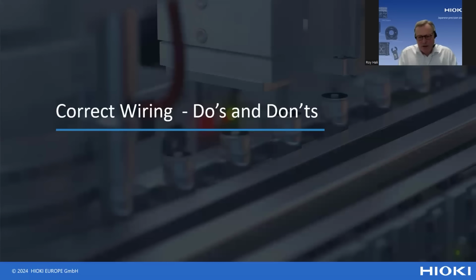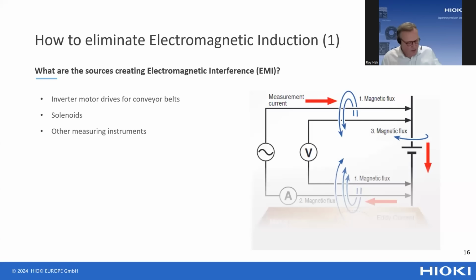So we start with the wiring first. What influences can the wiring have? The first thing to consider is that electromagnetic induction can influence the test results. How does that work? The battery tester uses a measurement current, which can be quite high, especially when measuring low internal resistance. For instance, the battery testers we use, for the low resistance range, use 1 amp.